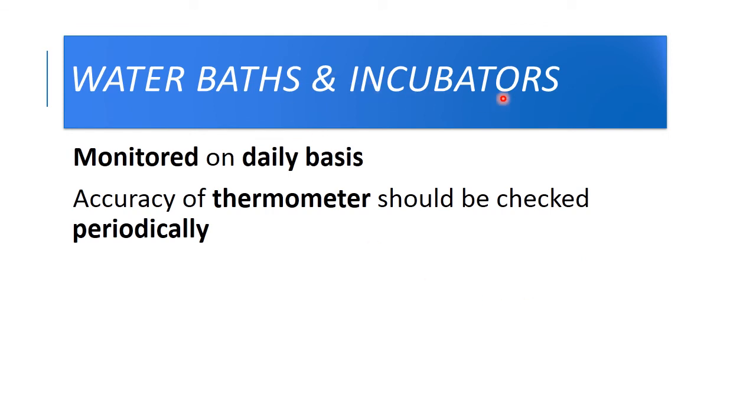Water baths and incubators. This is again thermostatic equipment. It should be monitored on a daily basis. Accuracy of the thermometer should be checked periodically.